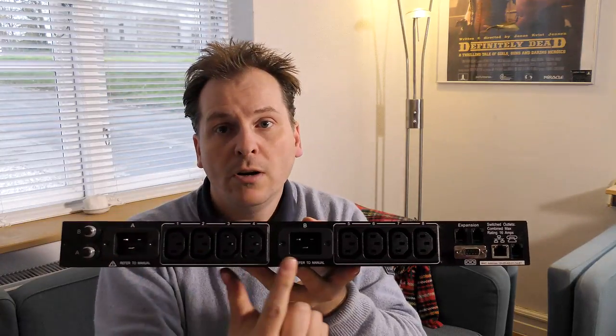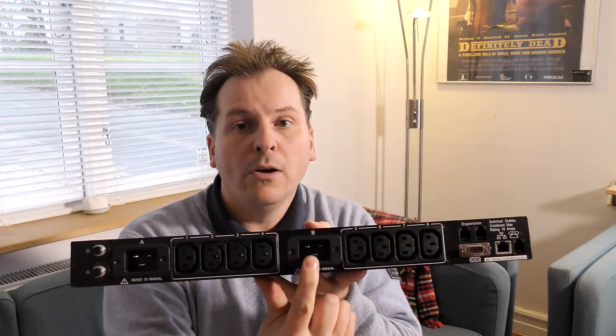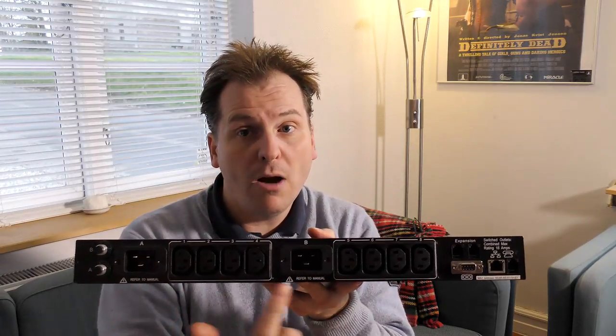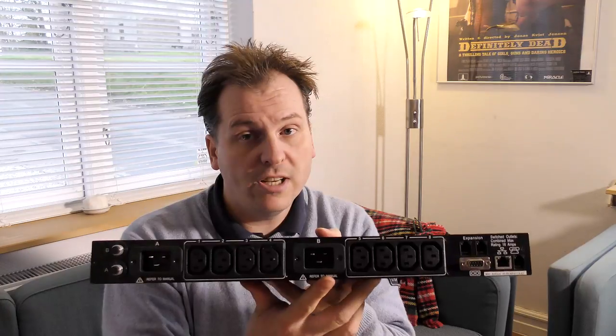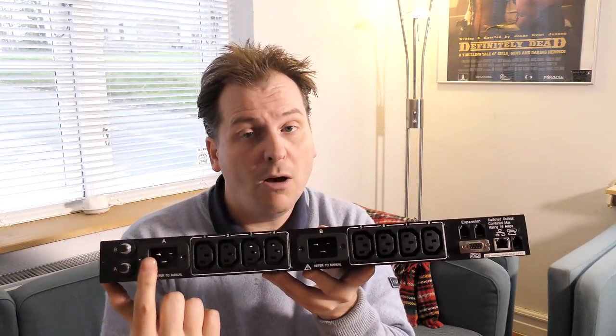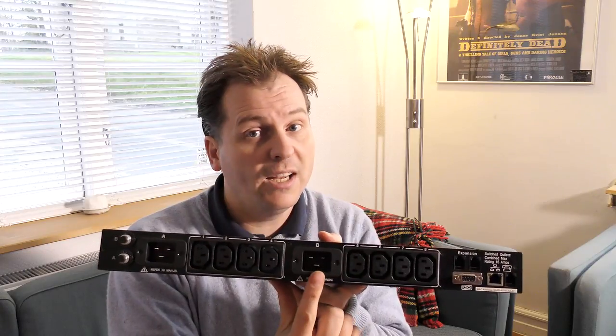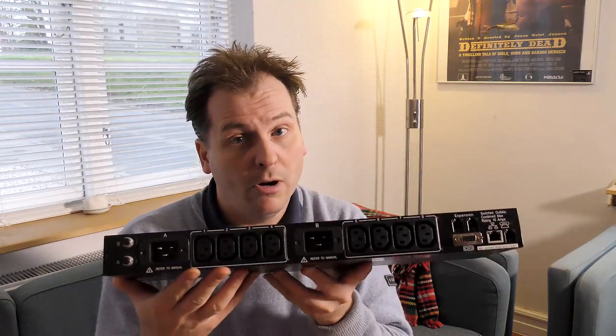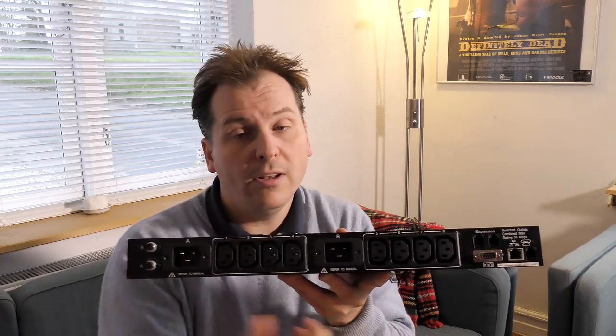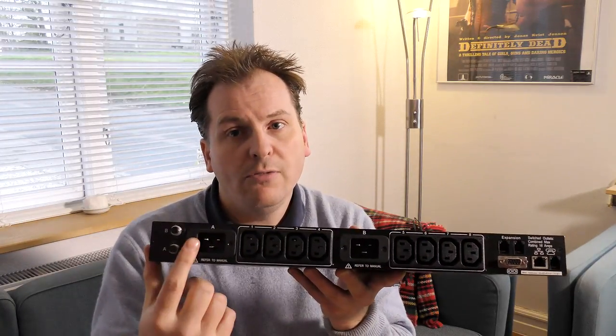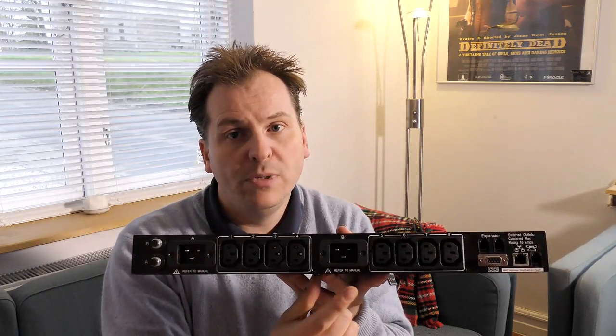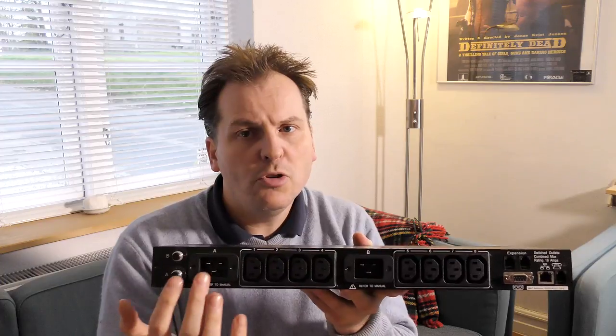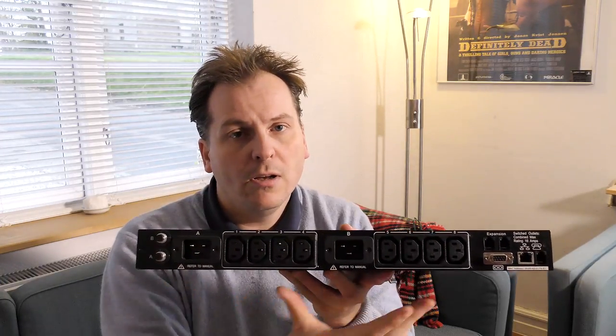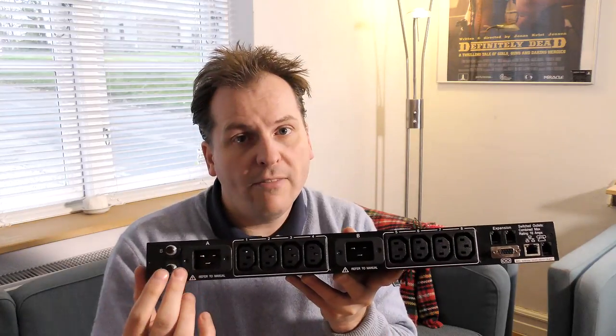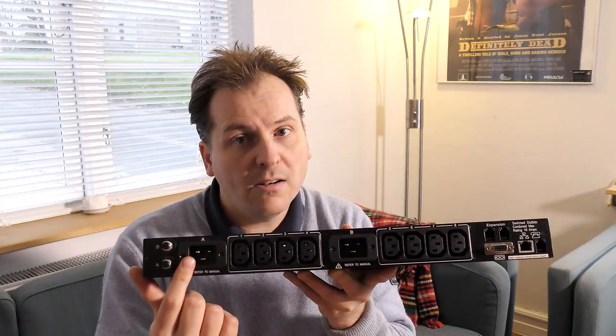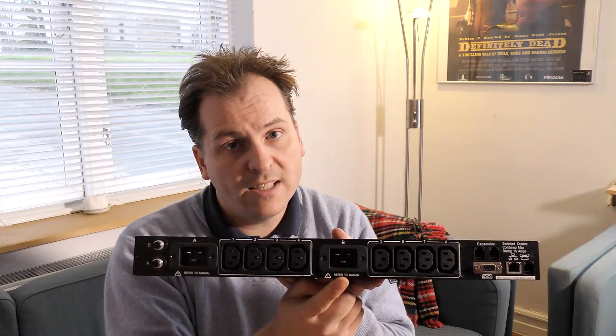You can put in one source here and one source there, which means that you can have two power sources coming in at your data center. So you can have a main power coming in here, and you could have a generator coming in here, and whatever there is power on will be put out through the other leads. So if you lose your mains and your UPS is connected over here, you might not want your UPS to be connected to this all the time. So you could have it set up so that as long as there is main on it, it's not supposed to be using the UPS power over here.